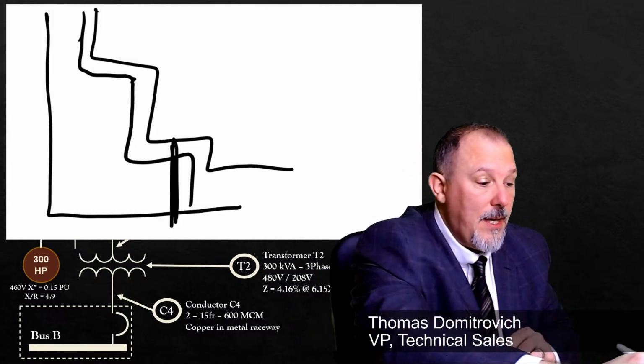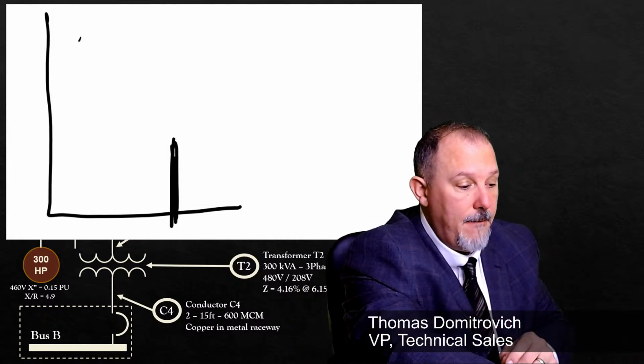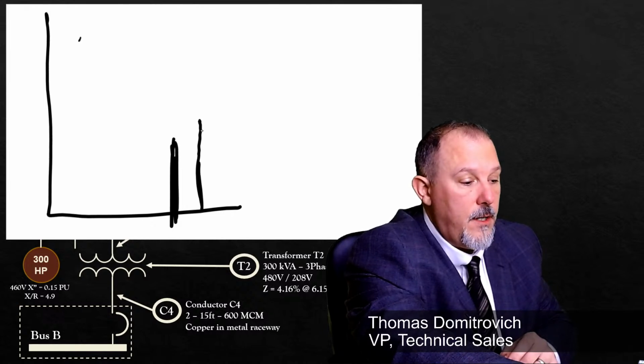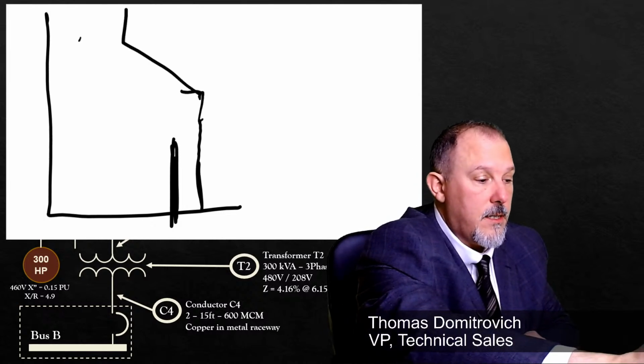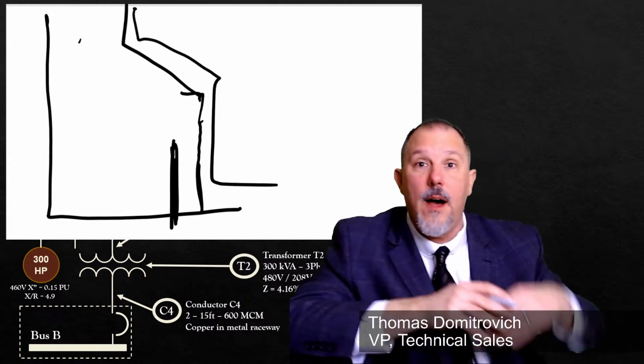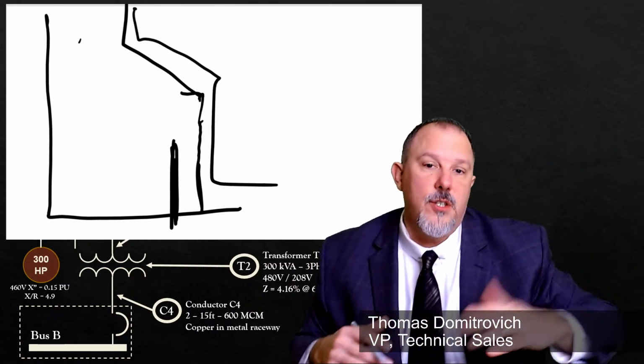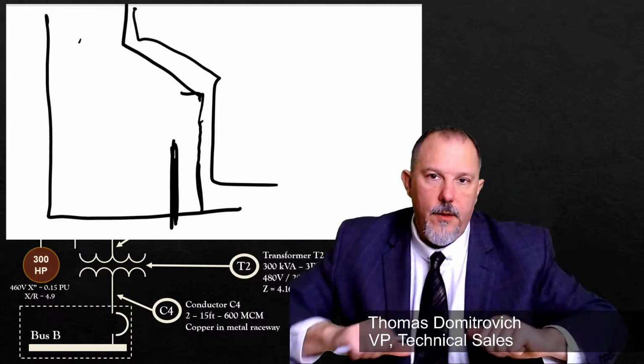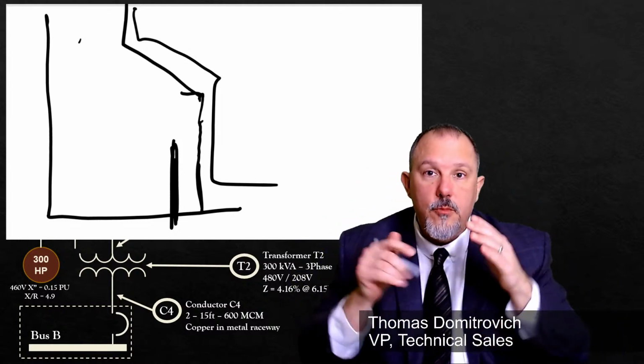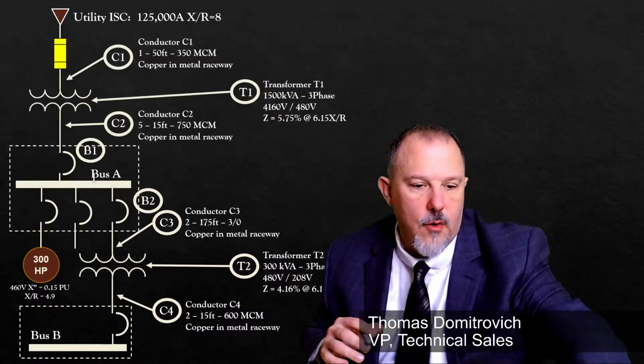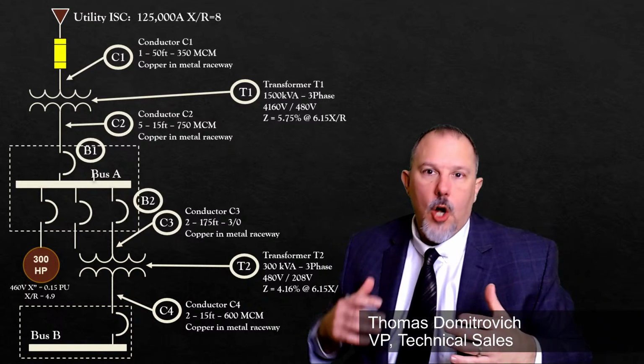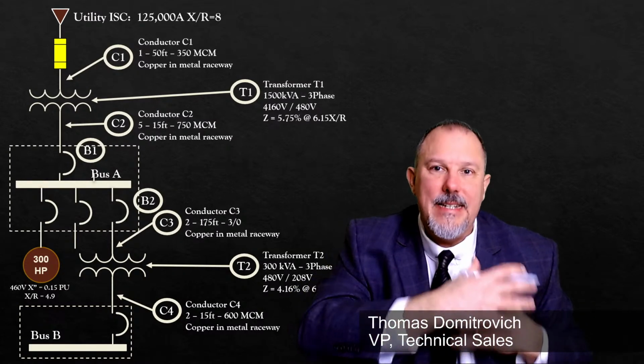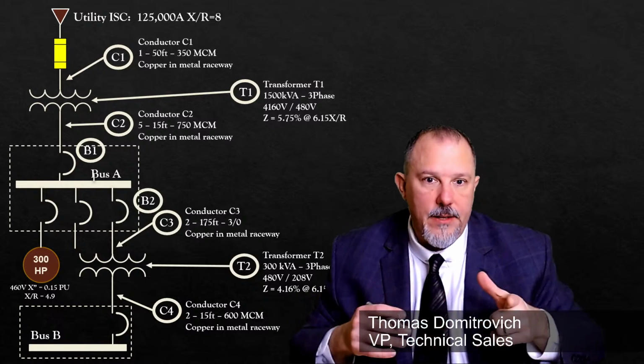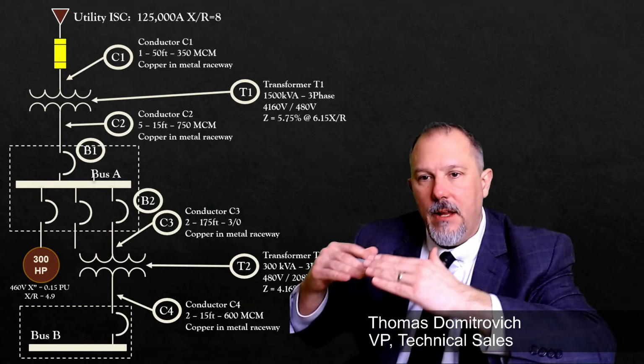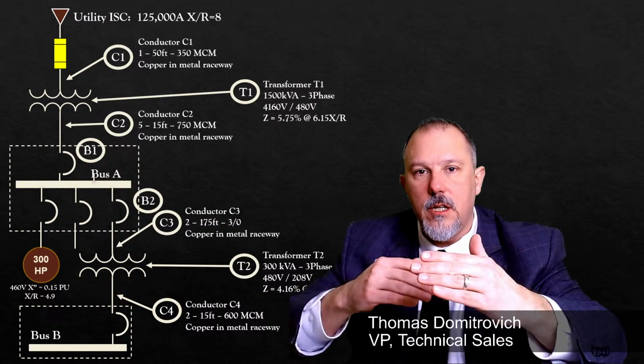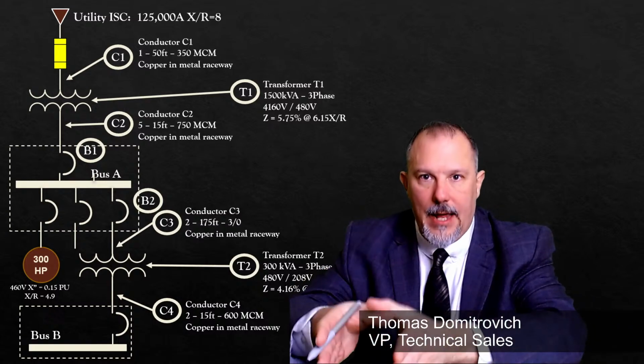But it could be that I don't have a short time delay, and what I really have is something that looks like this without a short time delay, and now I'm into the long time delay and well past 2 seconds, and my incident energy just went through the roof. So what you're doing with selective coordination is you're trying to balance reliability and equipment damage. And the reason is because as you move up into the power system closer to the utility, you're adding intentional delays.